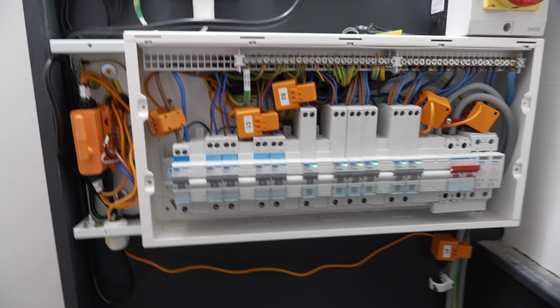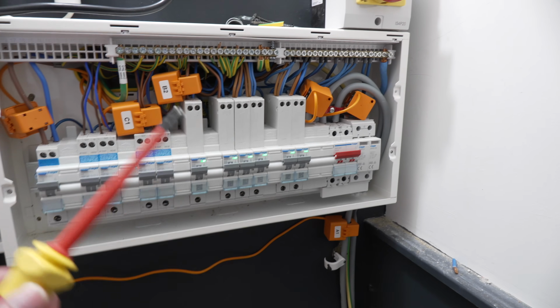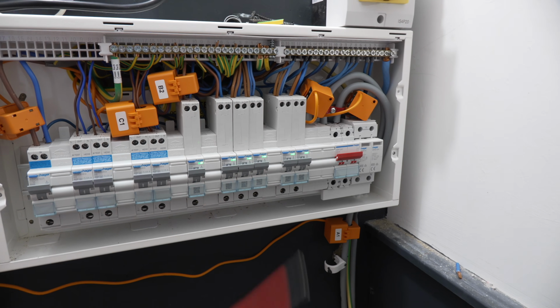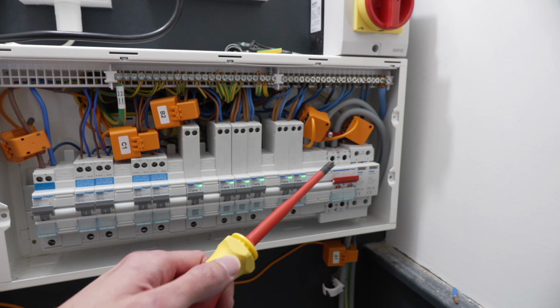It is all absolutely fine though, the cables all run neatly round, behind the breakers, behind the DIN rail, come up and out and into there, so it's all absolutely fine, but it is very tight. These are very large CTs. The other thing you'll notice that is lacking in here is the grid CT.